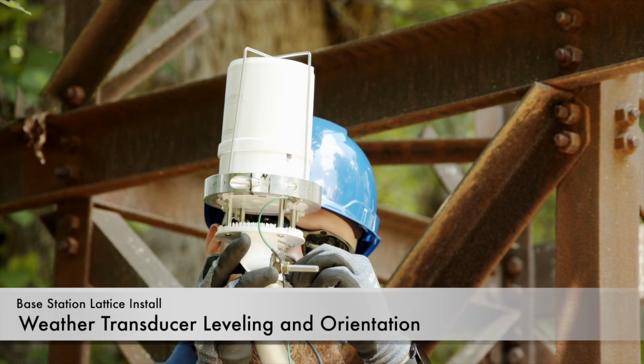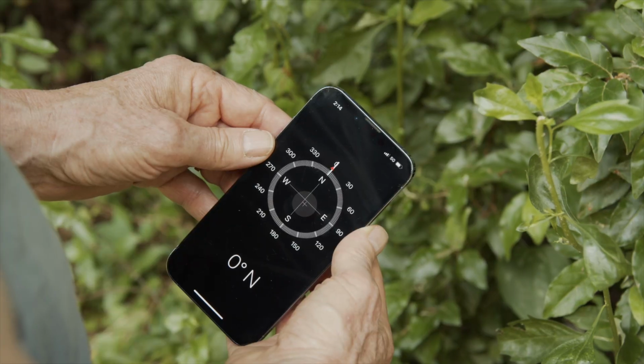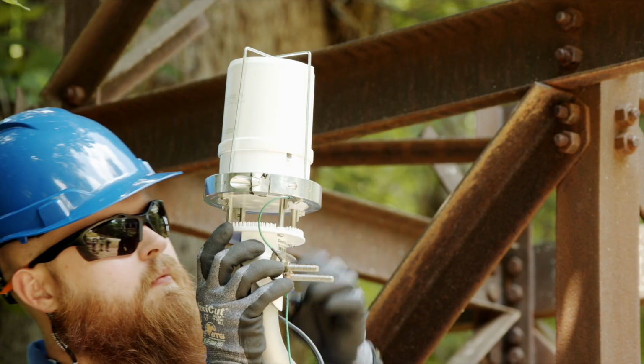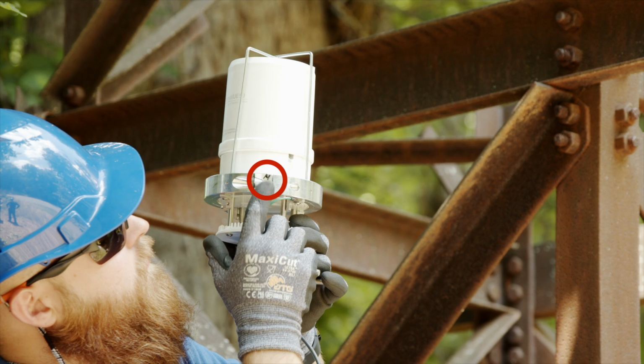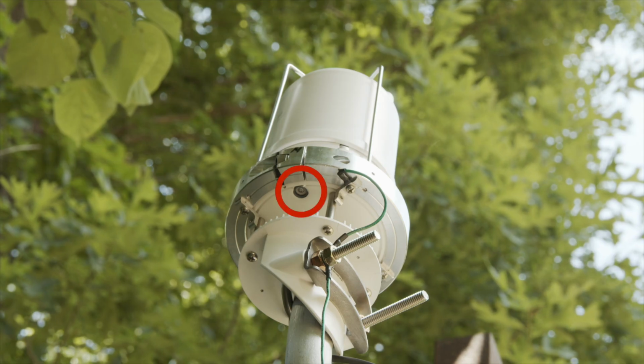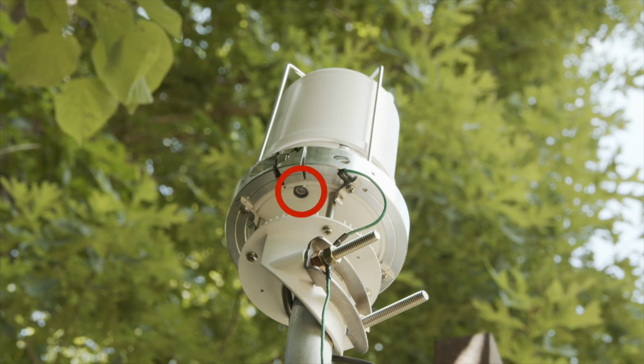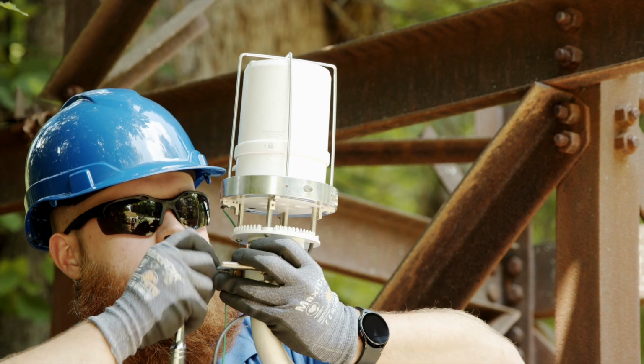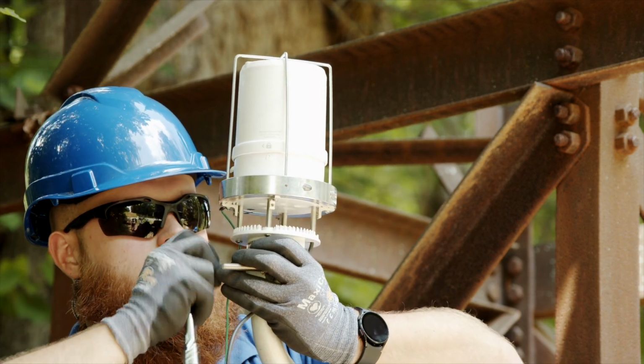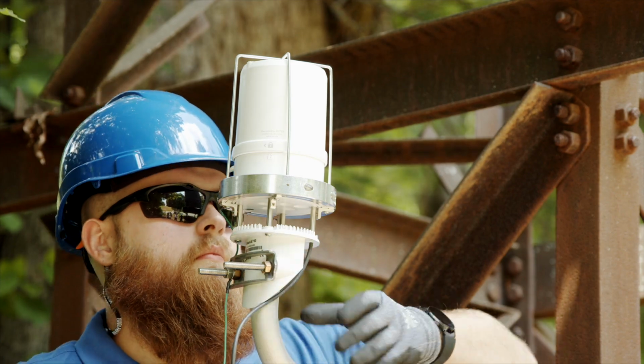Weather transducer leveling and orientation. Using a compass, ensure that the N on the weather transducer is facing true north, and level the unit using the bubble level located on the bottom of the monitor. Tighten the U-bolt so that the transducer is firmly in place and cannot be rotated.